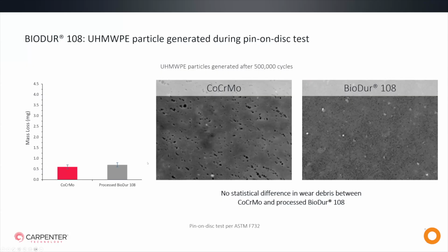After we completed the pin-on-disc wear test, we looked at surface contamination of the wear debris and also the overall pin mass loss. As you can see in the mass loss diagram, which is just a truncated version of what I showed you a moment ago, and also in the images here, there's really no statistical difference between the two in pin loss after 500,000 cycles.